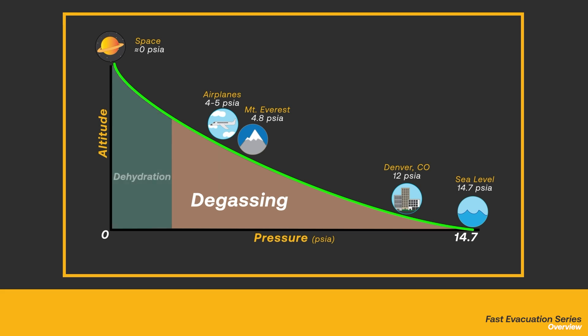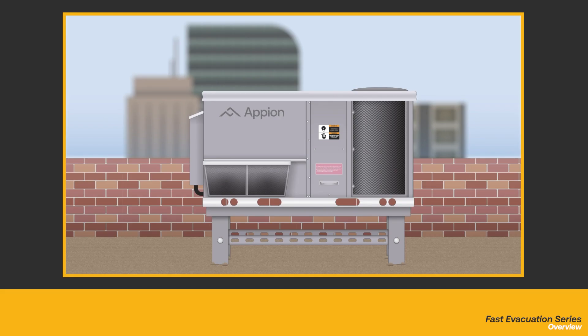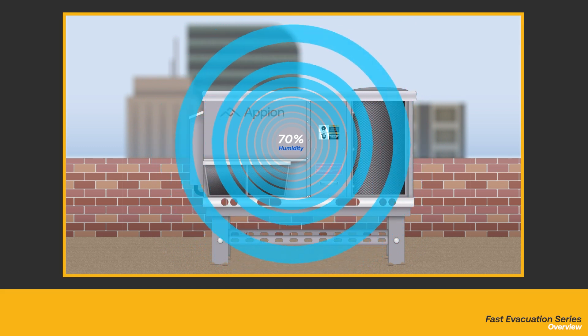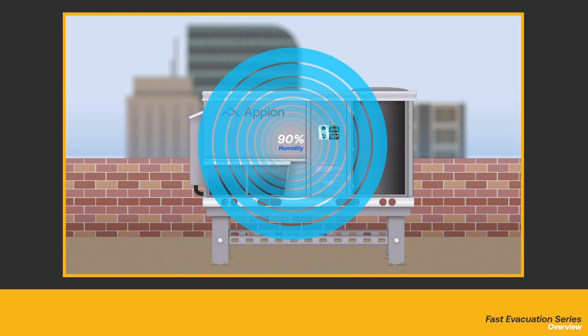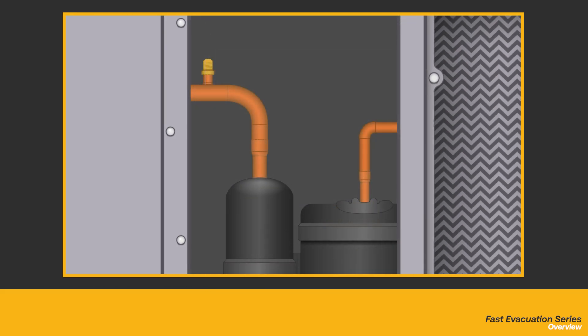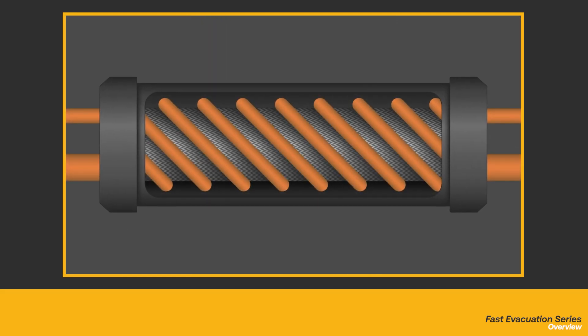But what's left behind can pose more of an issue. Moisture can be present in both a visible and invisible form. The air we breathe contains moisture. Depending on the relative humidity of the day, there will be varying degrees of moisture left in the system after the degassing process has been completed. In more extreme cases, water may have entered the system during installation or service, or due to failure of refrigerant-to-water heat exchangers on either the high or low side of the system.